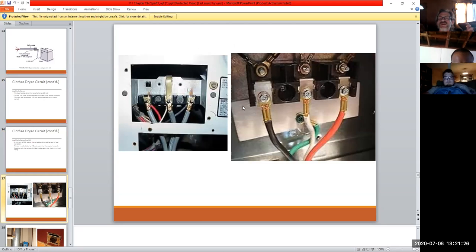And there's a couple of examples. Two styles of crimp-ons. Now, there's pros and cons to either style, believe it or not. So you have the open prong ones, and these are nice in the fact that when you loosen up the nuts, you can just slide that prong out if you need to change it out. Now the downside, of course, is, remember, this thing's going to be running, right? So you're going to have a certain amount of vibration to it. And given over time, yeah, the nuts probably shouldn't loosen up, but you never know. Things happen.